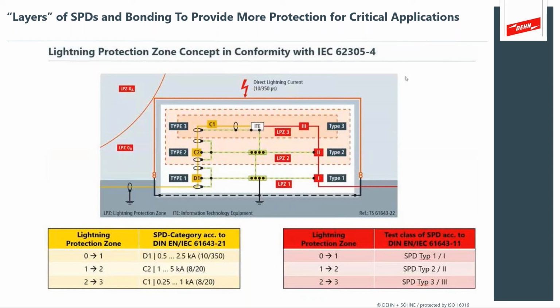And just as a point of reference for this presentation today, the application of SPDs in and of itself could be an hour-long topic, which I think we'll plan for our upcoming webinar series, because this really is a complicated and important subject of its own. How to select, and Stephen, you also mentioned, what are the surge current ratings? It's not just important to have a huge surge current rating, it's important that the device can actually handle, withstand and effectively dissipate that current. So, for instance, I could put a giant surge protection device at my service entrance and have a tiny ground wire or a tiny fuse, and now I've derated the whole thing, and it's almost a waste.